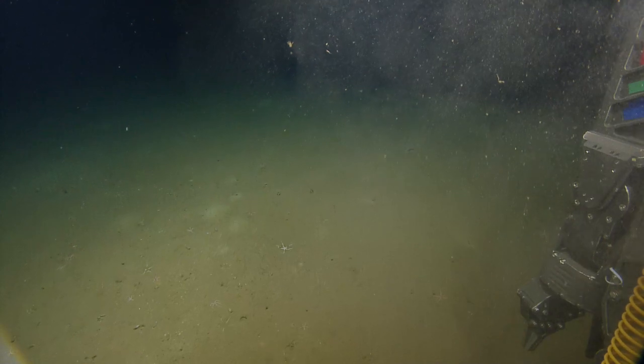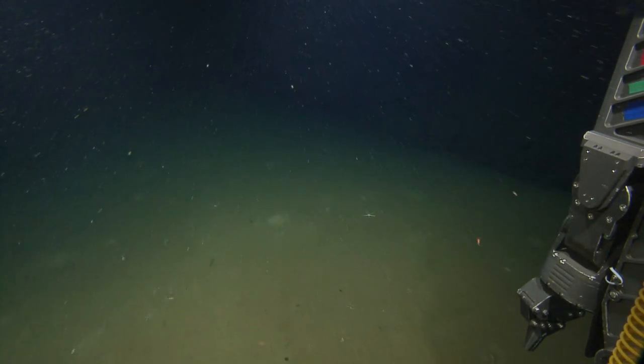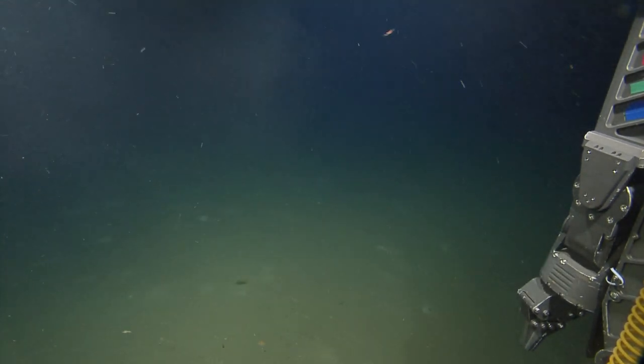Actually, a bucket lid would have been perfect for this. Yeah, the bucket lid. I didn't know if a bucket lid would be too disturbing to the seismometer. We make sure that we lock the sensing masses down from shore. So if it can handle me pushing it around on a pallet jack, okay, should be pretty good.